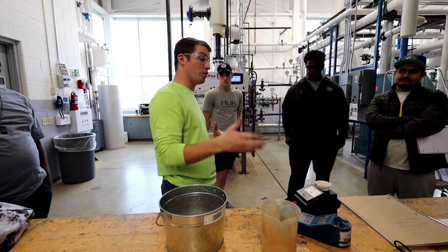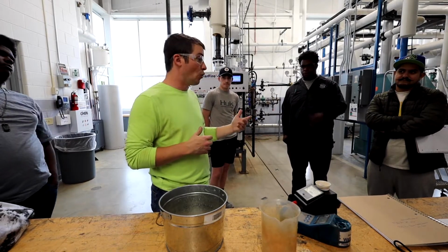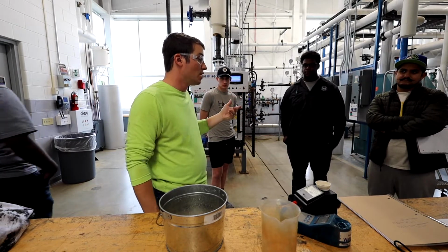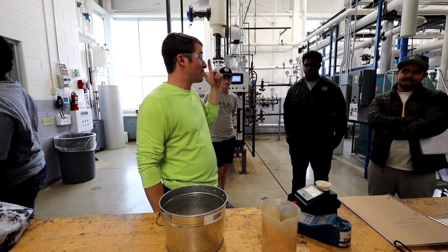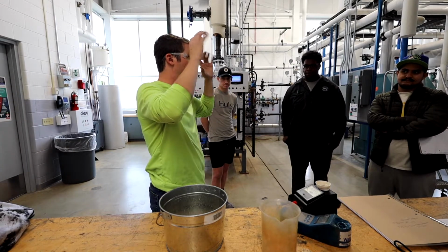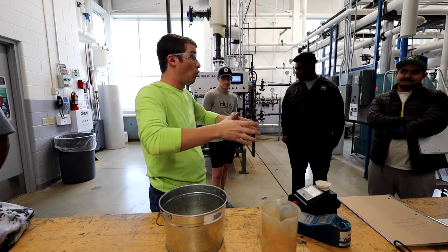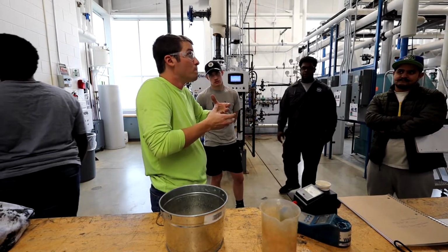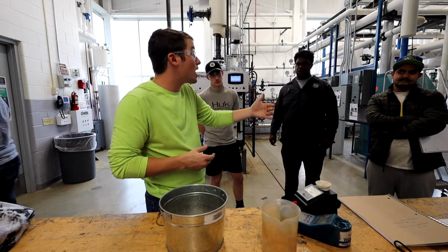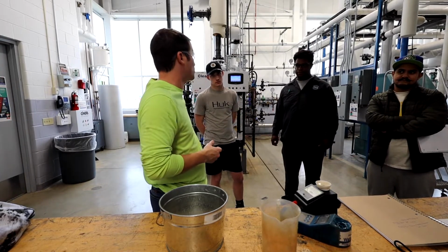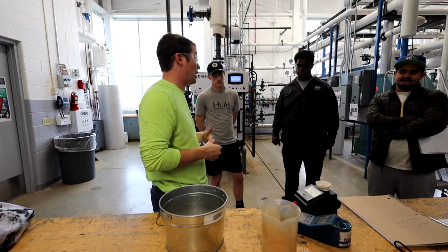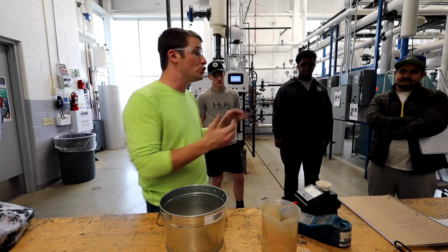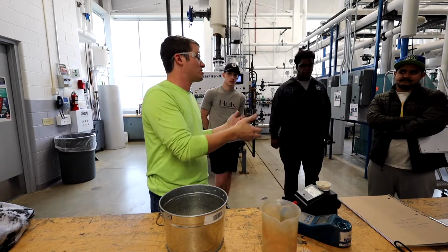So the ones that run really well, you're probably gonna have a lower reading. The ones that don't, or maybe they don't get a lot of condensate back because of the process. Like I have a customer, they make breadsticks. Most of their steam is used in proofers on the dough, right? Well, they don't really get a lot of condensate back from that process. They get very little actually. So our feed water conductivity typically is higher because it's a lot of just fresh water going in. It's not condensate coming back. It's not bad, it just is what it is, right? There's nothing we can do per se about their processes the way that it is.